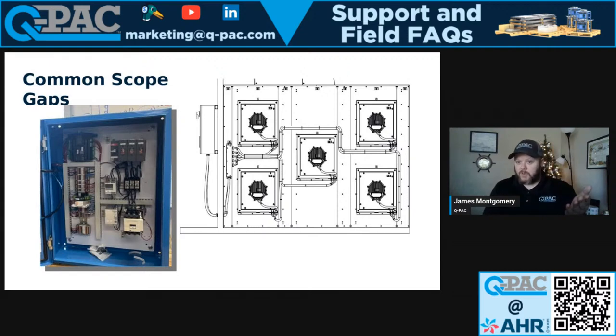And it's generally the electrical, it's low voltage, even though we call it controls. They need to run a separate conduit, whether that be flex or whatever your NEC requirement is, for the low voltage. They cannot share the same conduit, and it can't just be run willy-nilly. This stuff needs to be bonded and passed through, watertight, flex, like I said, whatever your code is, but that goes essentially right next to the electrical. And this gets missed a lot.